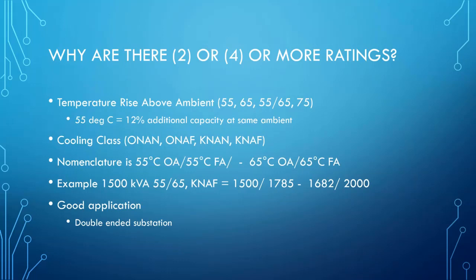You are going to get a transformer that is base rated at 1500 kVA, and it's going to rise 55 degrees C above ambient at 1500 kVA without the fans on. Okay. If you turn the fans on, now this transformer is capable of 1785 kVA, but still at a 55 degrees C rating. Then the 1682 rating is the rating with no fans, but we're allowing that same transformer to rise to 65 degrees C, which we've proved in the marketplace is perfectly acceptable.